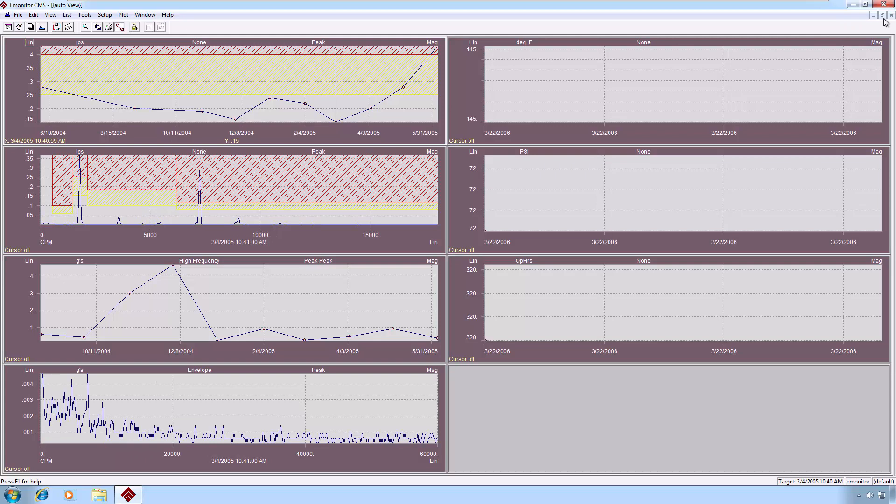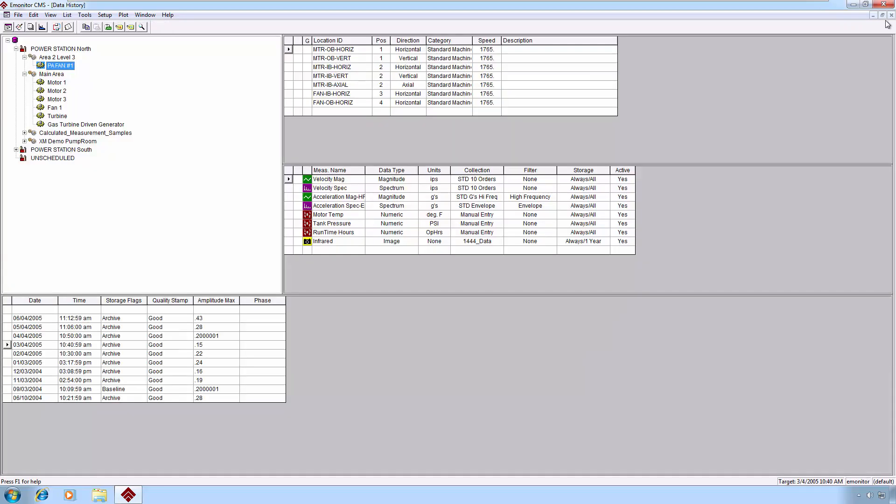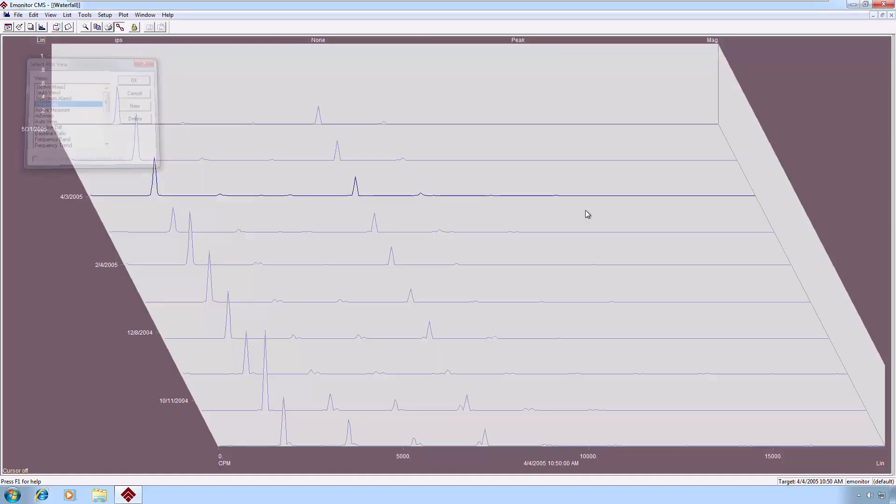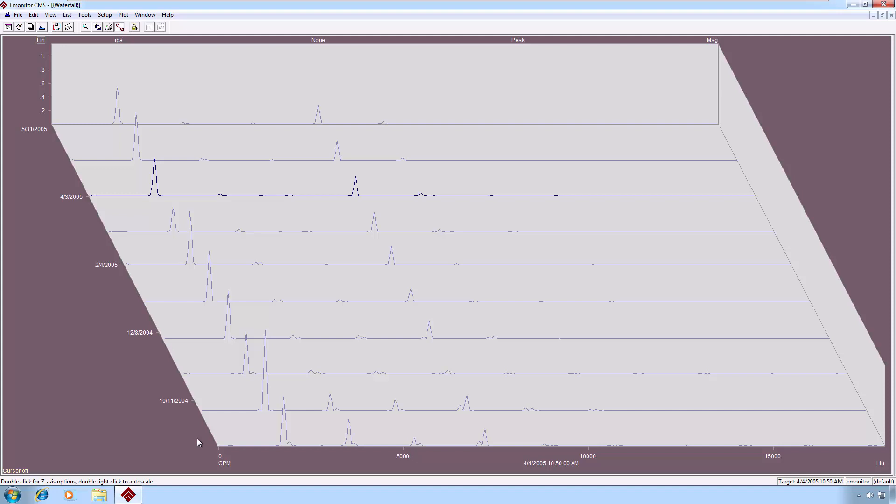Let's take a look at some other plot views. I'm going to once again open the plot view list, and let's select Waterfall. Waterfall gives us a history of our spectra measurements. You can see the oldest measurement in this sample is presented at the bottom or the front of the plot, and in the back of the plot, you'll see the latest measurement sample we have for this particular measurement.